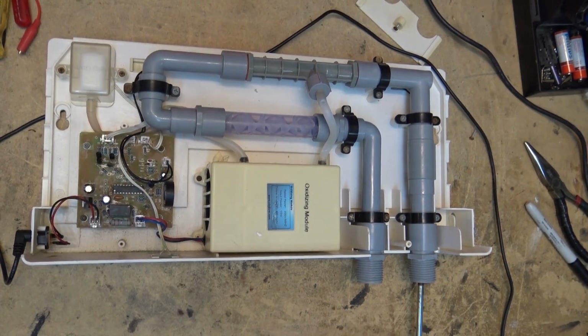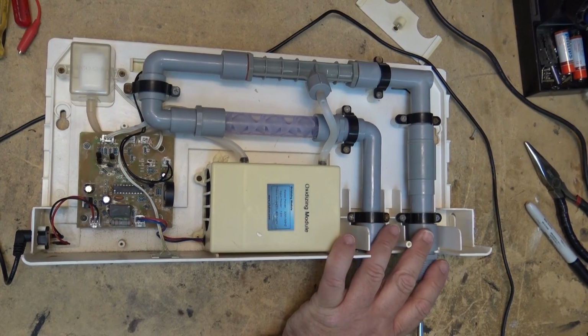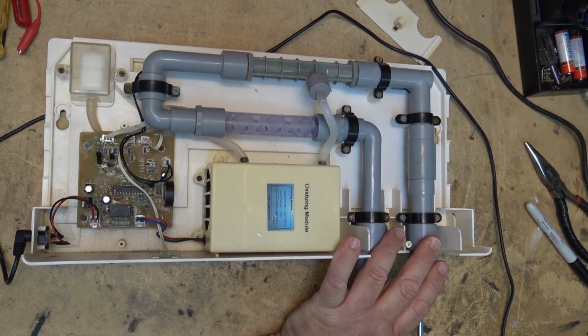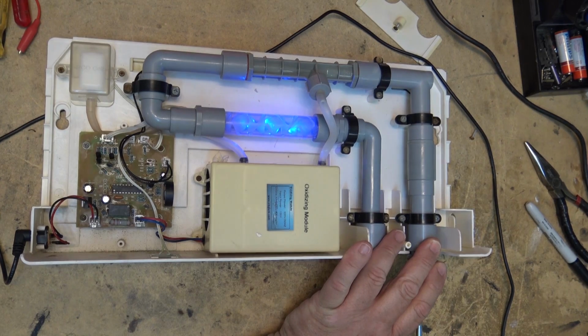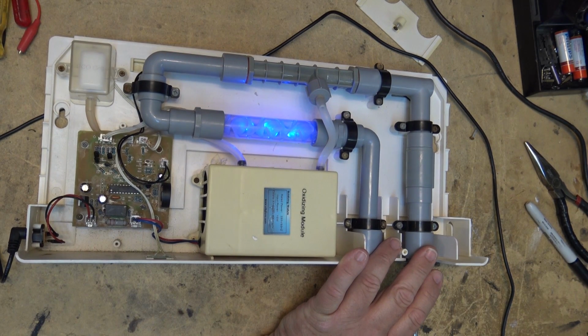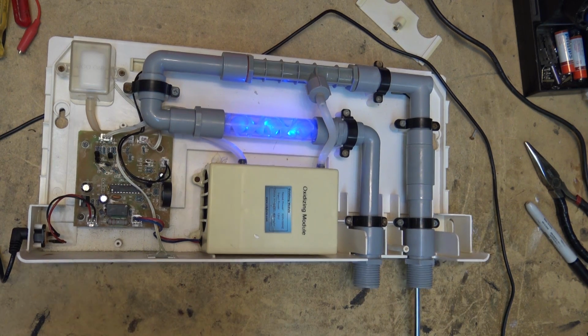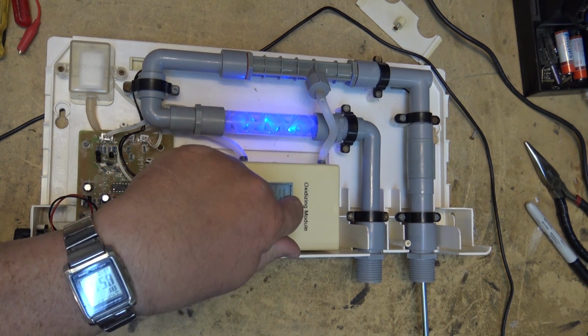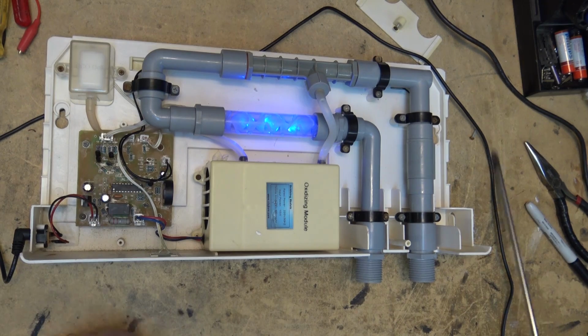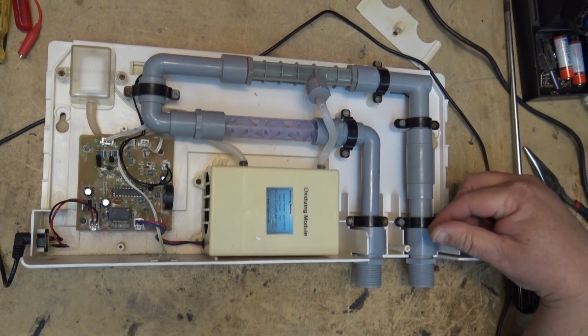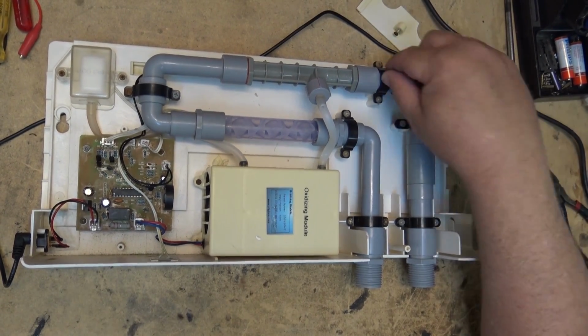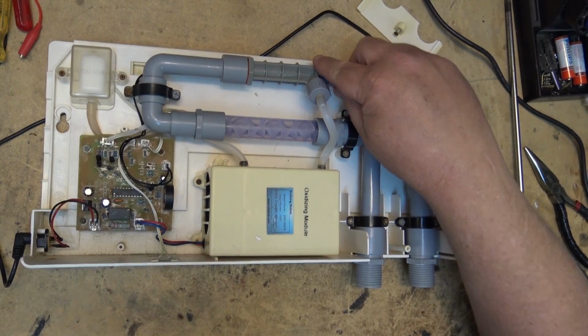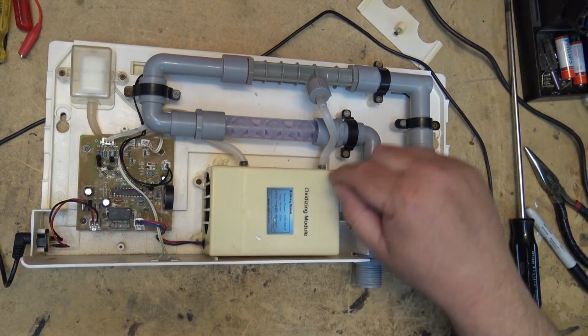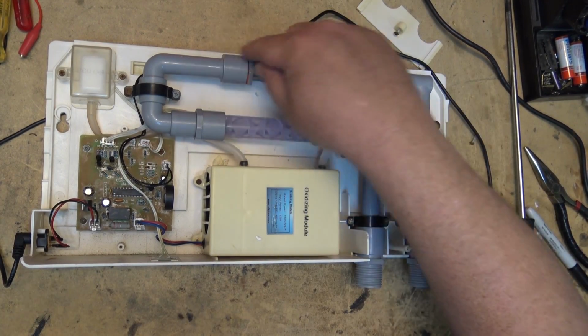When it's operating, when the water enters and presses the water flow switch, you get blue lights that light up to let you know the ozone is on, to make you think that's actually where the ozone's coming from, when it's actually coming from the ozone generator here. Water passing through the water inlet goes through this venturi, which creates a vacuum that draws ozone generated by the ozone generator in through here.